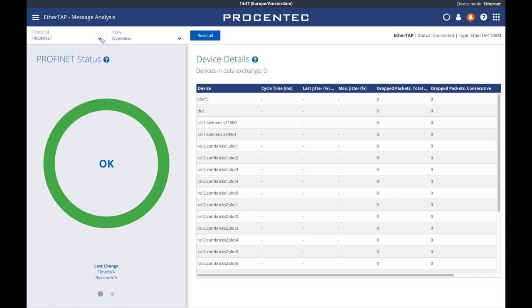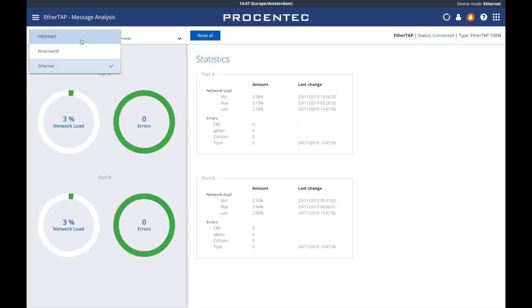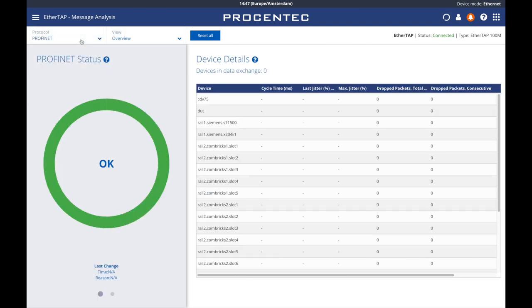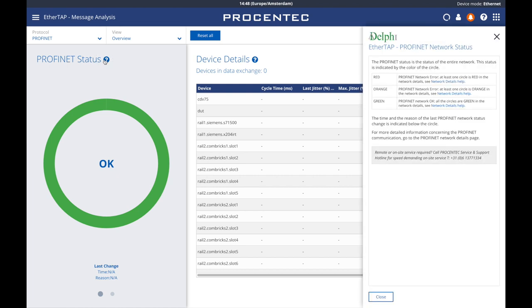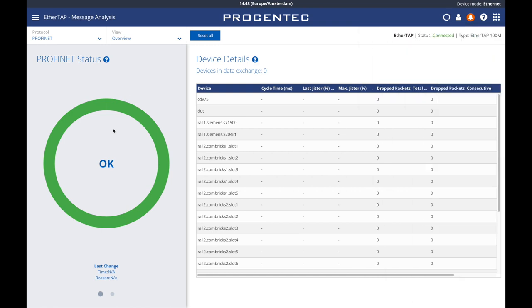As you can see, the protocol is set here. Depending on the license you are using, you can switch with the protocol drop-down menu between Profinet, Ethernet, and our latest Ethernet IP. Each protocol will show you different information. Here we can see the overall status of the network with the device details chart next to it. If you want to know what you are looking at, you can always click on the question mark icons and Delphi will appear informing you of what you are looking at. We have a general status of the entire network — the color-coded ring shows us if everything is fine in Procentec's traditional stoplight system. This status ring is a summary of the passive information OSIRIS is analyzing.